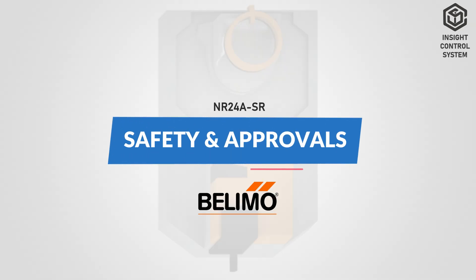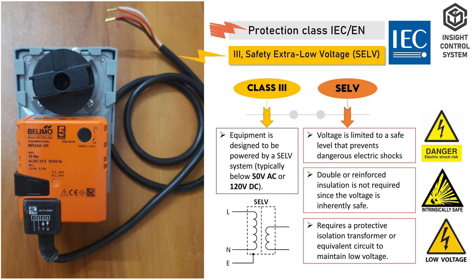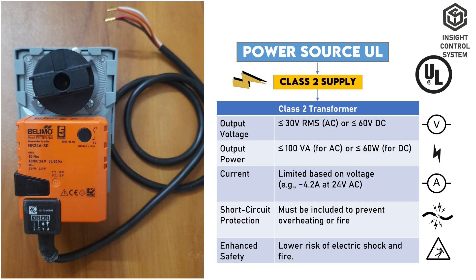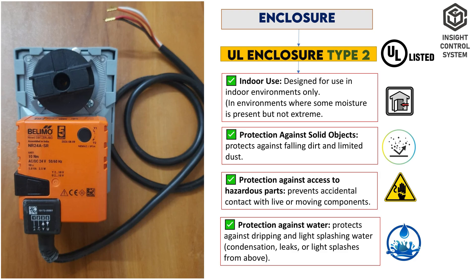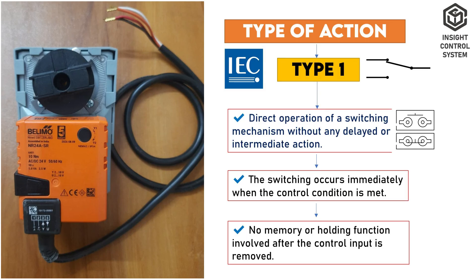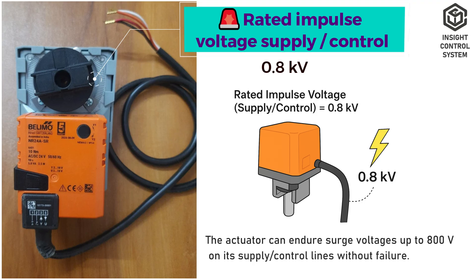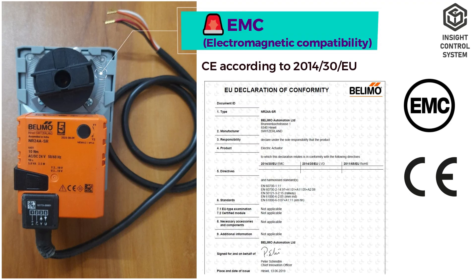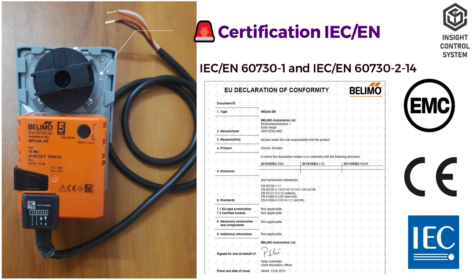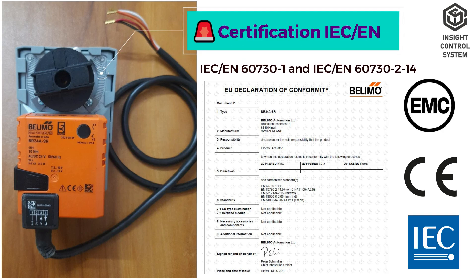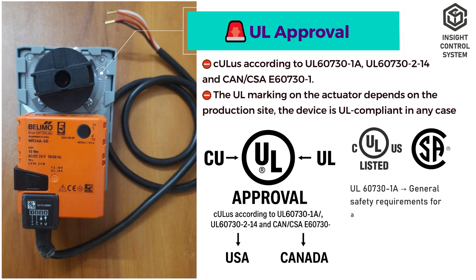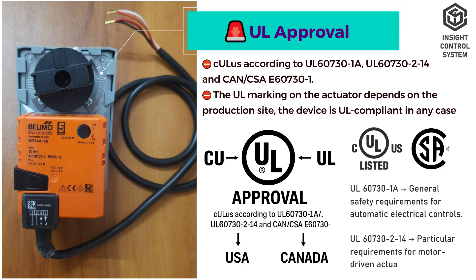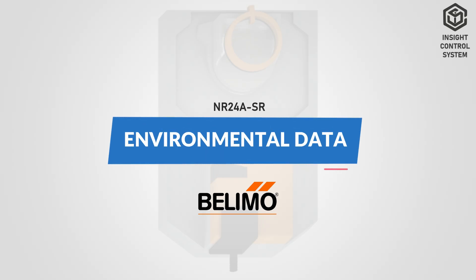Safety and approvals: protection class IEC EN is 3 — safety extra low voltage. Power source UL is class 2 supply. Enclosure is UL enclosure type 2. Type of action is type 1. Rated impulse voltage for supply and control is 0.8 kV. Electromagnetic compatibility is CE conformity. Certification is IEC EN. UL approval covers Canada and the United States by Underwriters Laboratories and the Canadian Standards Association.